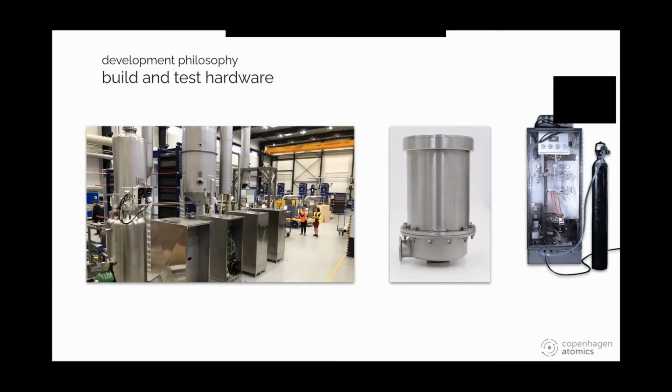And what allows us to do this is basically our pump, which is a canned rotor pump. That's very different from the cantilever type pump they had in the MSR days, where you have a pump at the bottom, a long shaft and a dynamic seal, and then a motor at the top that you keep cold. This design is all compressed into a canned rotor pump, which means the rotor and impeller are together and actuated electromagnetically, and that allows us to just weld the whole thing up and not have any dynamic seals.